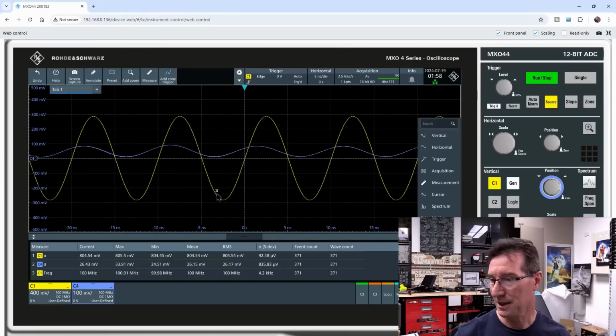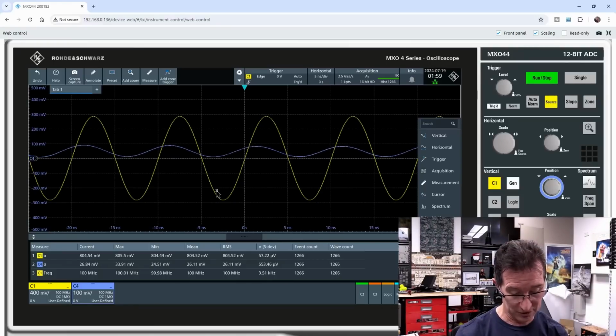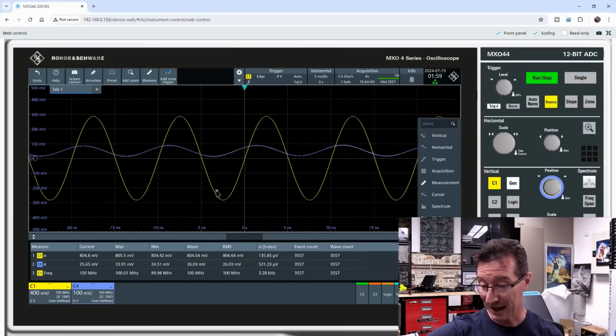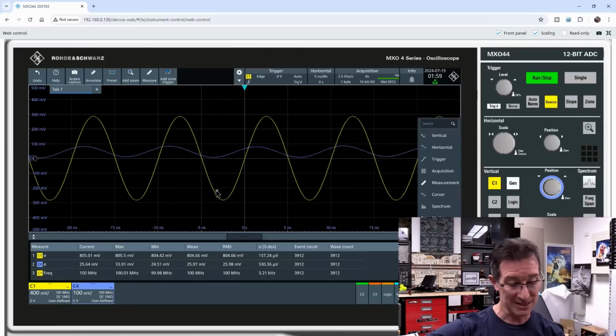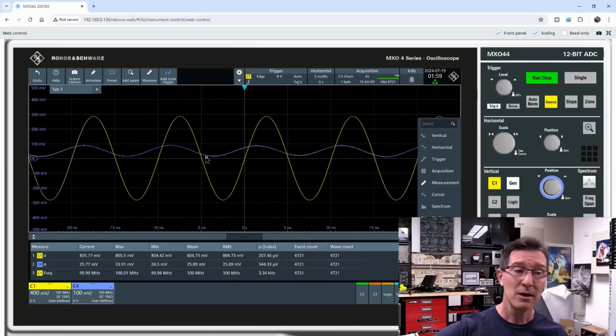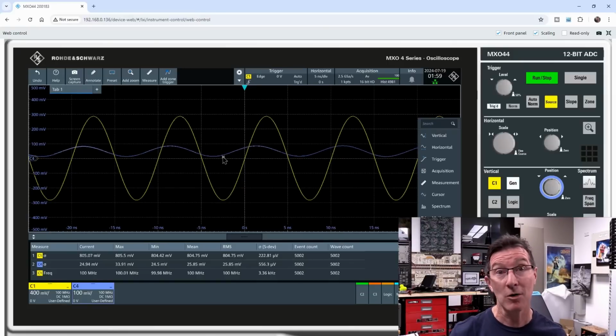All right, so let's reset our stats here. And what do we got? We've got a mean of 26.2 millivolts, divided by 804.5 millivolts. We get log of that, and we multiply that by 20, and we're getting minus 29.7, pretty close to 30. And what is our spec at 100 megahertz? Minus 26 dB. So yeah, it meets the spec. So it's a reasonably decent probe for CMRR.